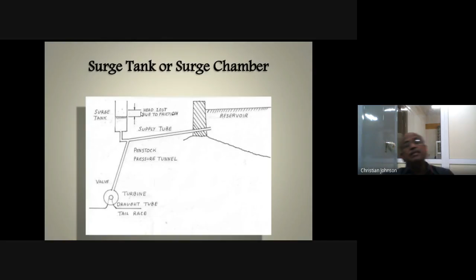If such a tank is not available, the entire pressure will be returning from here, and then it will try its best to come into the reservoir. During the course of time, it will eject higher pressure. This point, having that angle change, is one of the weakest zones. The penstock can really burst if this stop action goes on continuously during the course of time. It may weaken that point, and there is a possibility of bursting of the penstock.